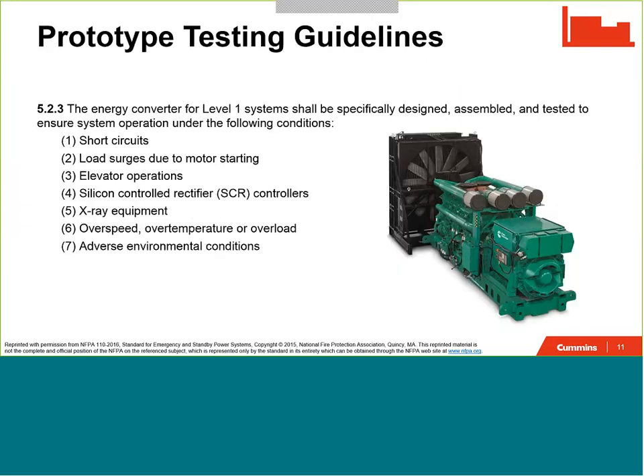The next thing I'll note here, and this is actually what's called out by NFPA 110, it lists all these seven items, and it says these are the prototype testing requirements that NFPA 110 has for a generator set manufacturer. The concern I have here that I brought up earlier is that this is the level of detail that NFPA 110 provides. It does not go into significantly further detail than what you see here.